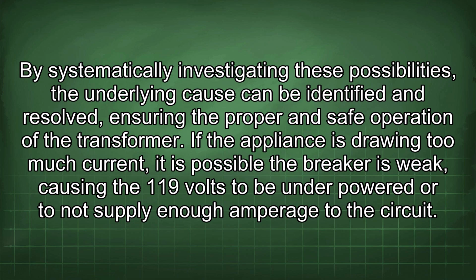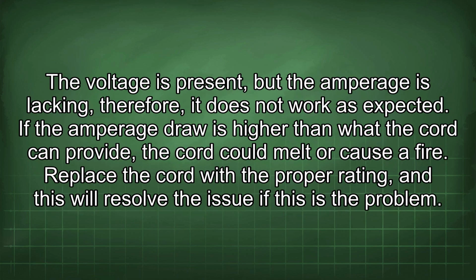If the appliance is drawing too much current, it is possible the breaker is weak, causing the 119 volts to be underpowered or to not supply enough amperage to the circuit. The voltage is present, but the amperage is lacking, therefore, it does not work as expected. If the amperage draw is higher than what the cord can provide, the cord could melt or cause a fire. Replace the cord with the proper rating, and this will resolve the issue if this is the problem.